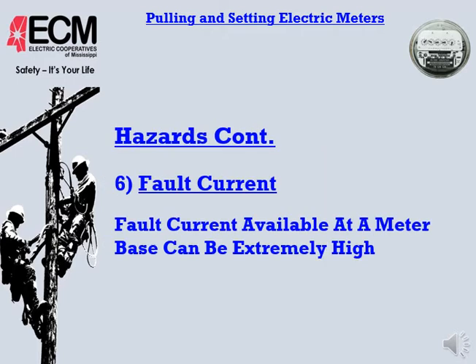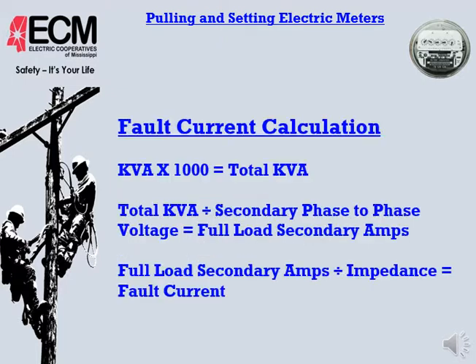Of course, the biggest thing we want to talk about is going to be fault current. And fault current, again, is one of these things we think about. It should be one of the things we think about on everything we do. Fault current available at a meter base, something as simple as a residential meter on a house, 120, 240, 3-wire, single phase, can be very high, can be extremely high. And with that being said, fault current calculation. I'm going to explain to you how to figure out your fault current at any given location, whether you have an overhead transformer or a pad mount transformer. Either one, it's going to be the same.